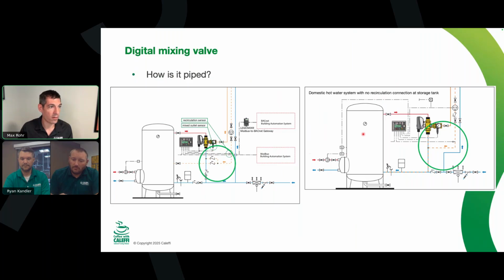That's why we publish both of the diagrams, because it can depend. But if you're going to troubleshoot a system and you're having issues with it, take note of where the check valves are. Double check that they're pointed in the right direction. We're not going to name names here, but I don't know if you guys have ever had a check valve that's been installed the wrong direction. That can really screw up this type of piping for sure. And that's where a dual union check valve is nice too. You can take it out and flip it over without having to repipe anything major.